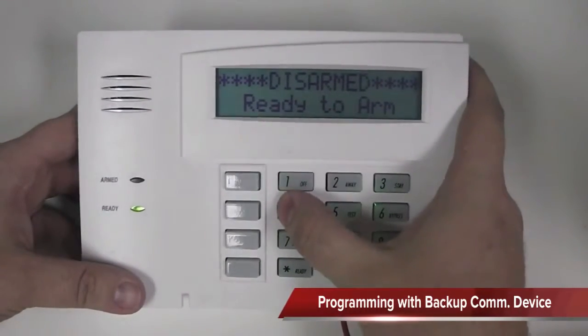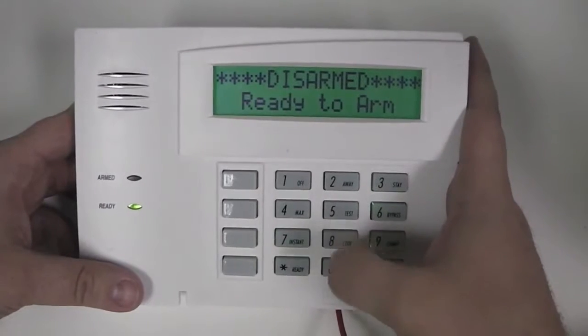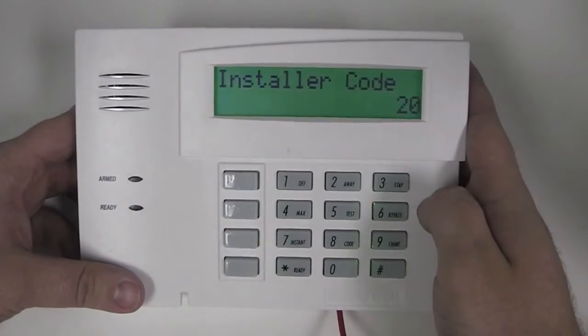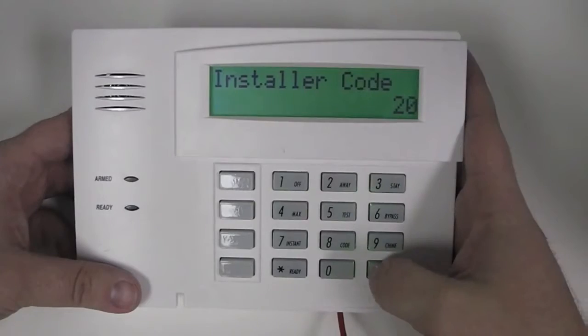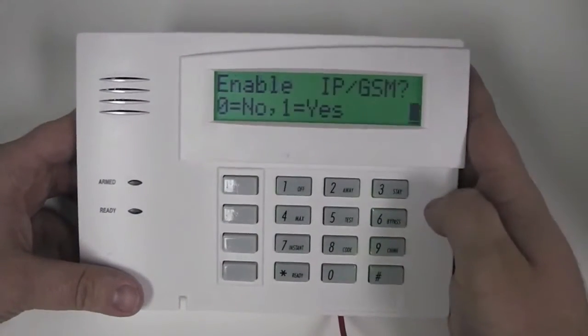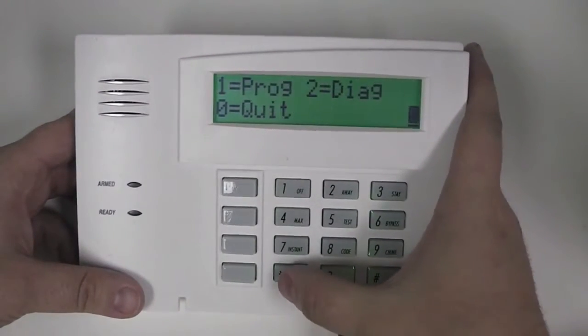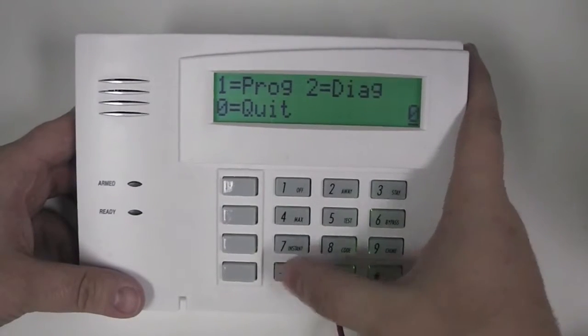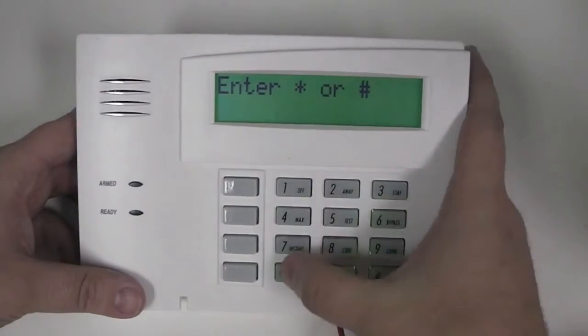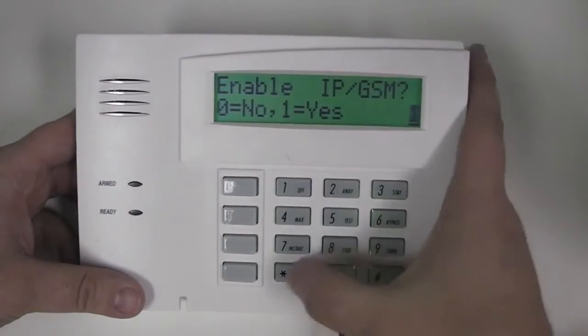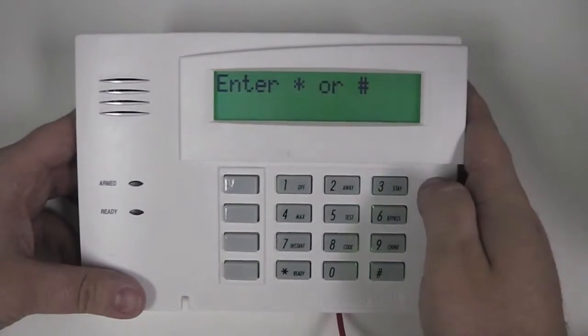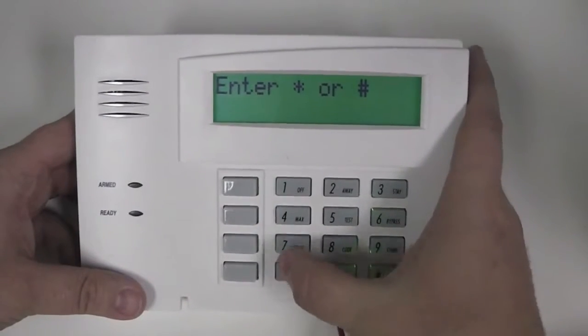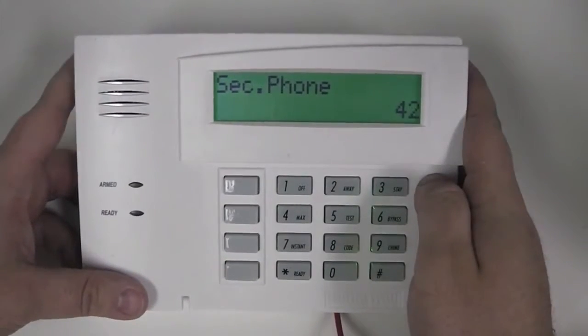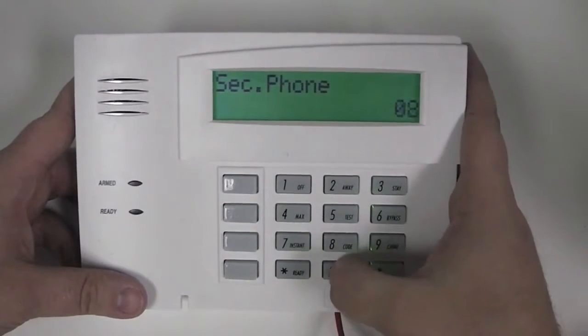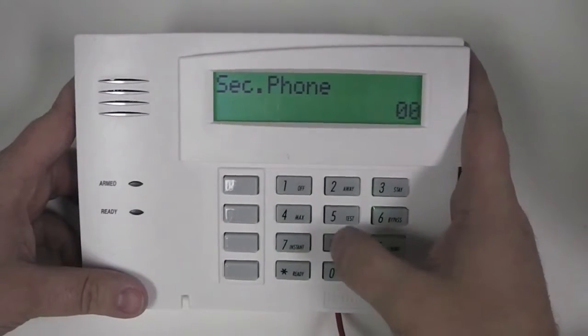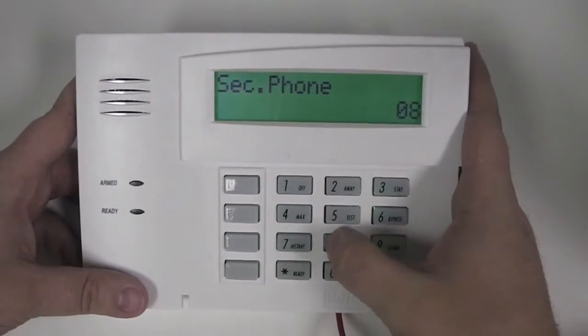We'll now look at your Vista alarm panel and find out how to program it with a backup communicator. You want to enter programming by entering your installer code plus 800. You want to make sure that *29 is enabled. This is to activate the IP/GSM, which is what the Vista panel thinks we emulate. We can move on to section 42. This is where you enter the secondary phone number for the backup communicator. You want to enter your central station receiver number into this field.